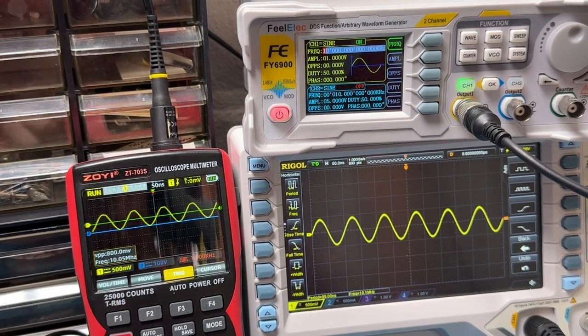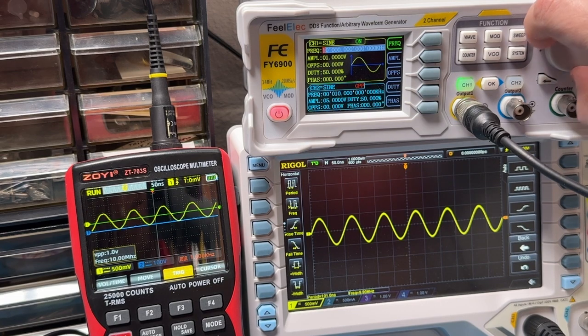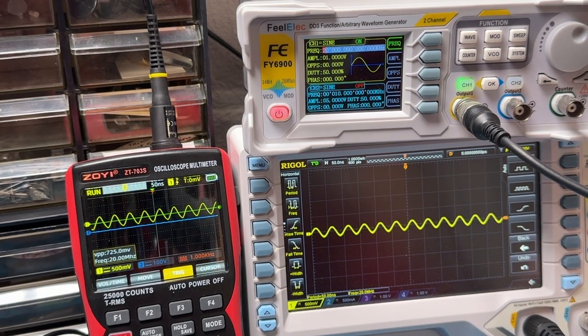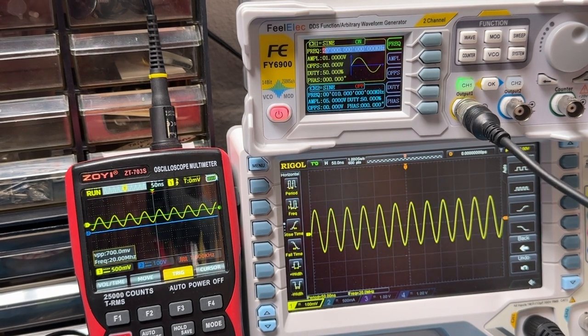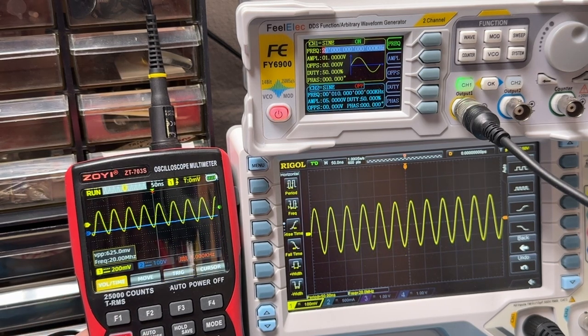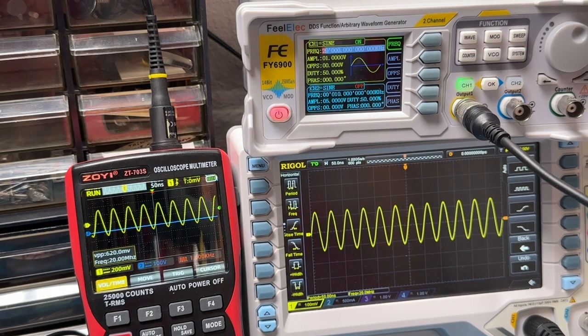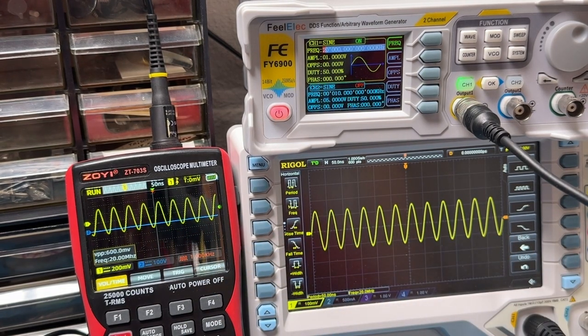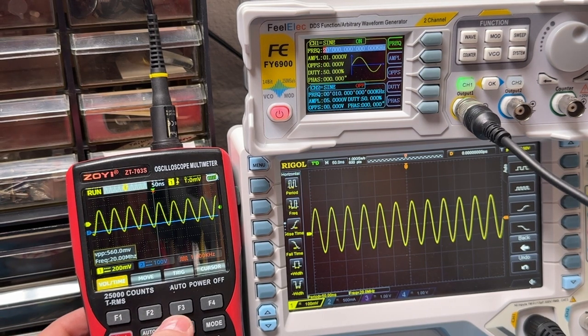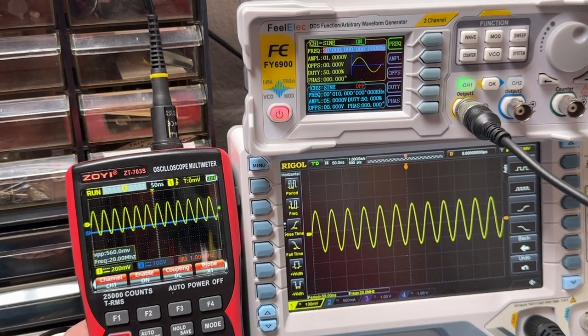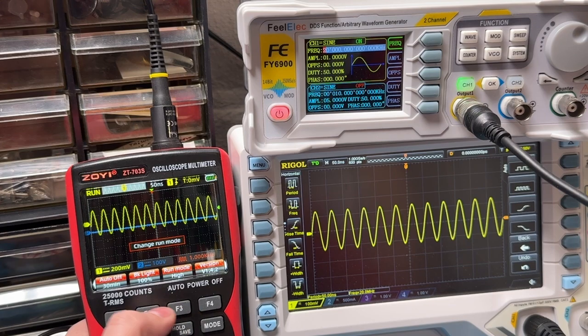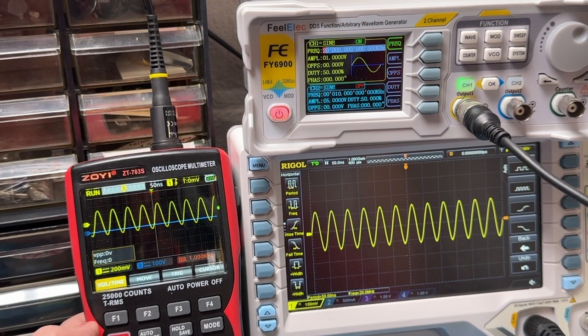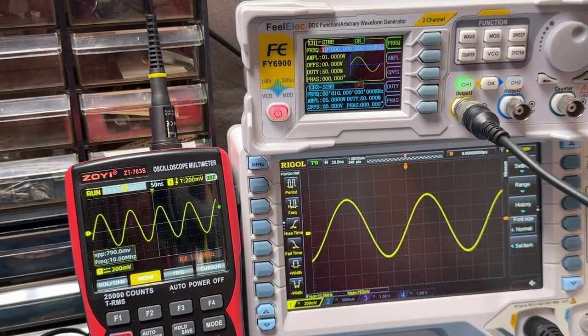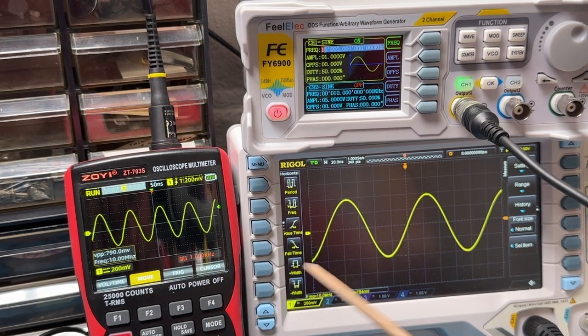Now the Zoyi is supposed to have a maximum frequency of 50 megahertz, and so I'm just going to start bumping up the frequency here. So that's 20 megahertz. We'll just change the vertical scale a little bit. There we go. And similarly here. So you can see that at 20 megahertz, there's a little more jitter in the display. Now, for the Zoyi, it says that as the frequency increases, we need to go into high resolution mode. And I'm going to turn off channel 2. Now, after some adjusting, I've got a 10 megahertz signal, and so we can see that both of these units are agreeing. 10 megahertz here, 10 megahertz here.